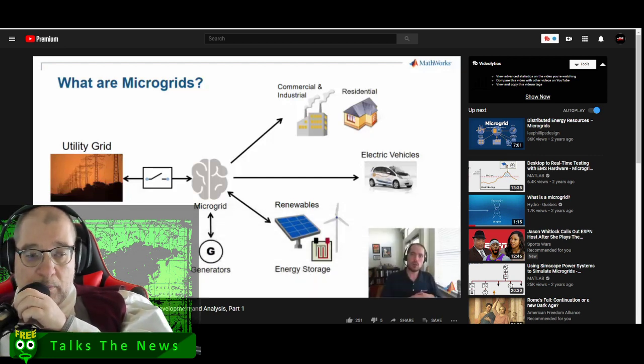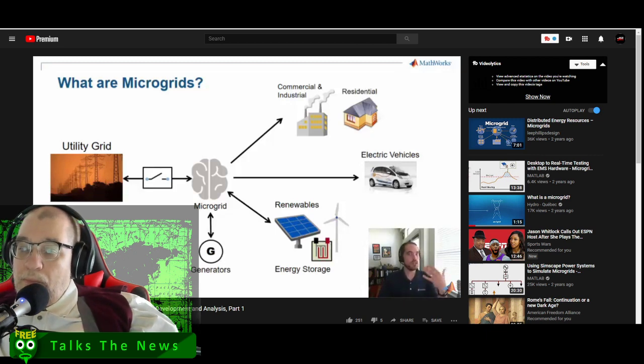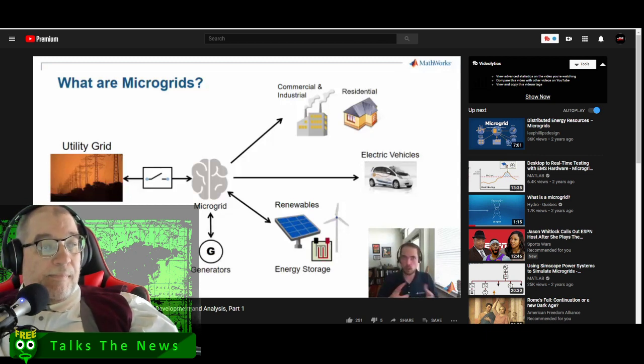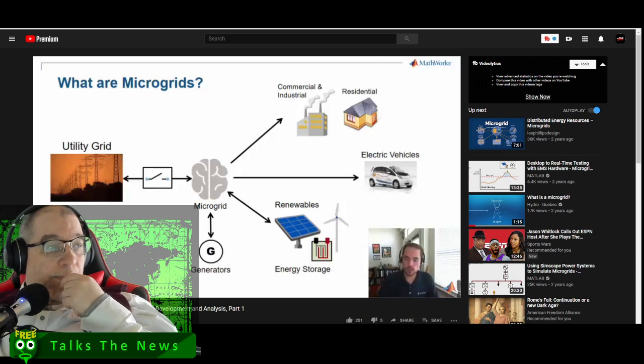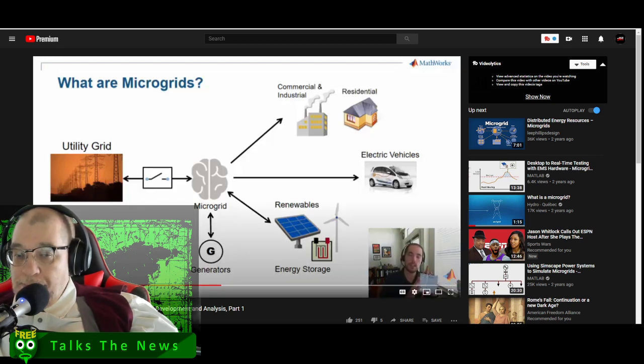Now, if we look at systems that are more distributed, like the microgrid, they're quite a bit different than the traditional utility structure. So traditional utility structure, we have centralized generation, power gets distributed down through the distribution network out to consumers. The microgrid concept and other distributed power systems are much more distributed. We have localized generation, be it through diesel generation systems or other renewable systems. And these all have to be coordinated, right? And so that's the job of the microgrid controller. The software that defines and controls these systems is really critical, because we're not only operating independently here, we can connect up to the utility grid as well. And so ultimately what we're going to be working with is a system like this. So this is an industrial control system. This is a PLC specifically, but these are the things that are actually going to be controlling the grids out into the field.